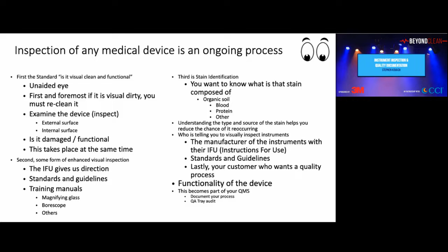They want a clean and functional, sterilized or HLD item used on them. They don't want a dirty scope or dirty instrument. You make sure it's functional. If you put a QMS process in your department, you can do it. You can do tray audits. There's a whole lot of things you can do. When it comes to cleaning equipment, it's the same thing. Man and machine get together. They're imperfect. Things are going to happen. Do regular inspection and testing.